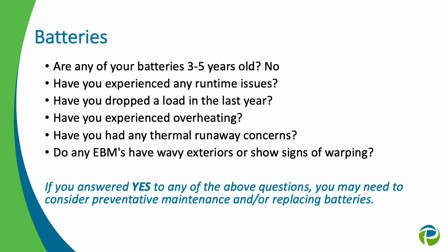And thermal runaway can be really dangerous because if you think of a chain of batteries overheating, that's just one big hot mess of a line, and that can cause fires very, very quickly, much more quickly than a smaller battery overheating. So thermal runaway is a huge concern. If you have any overheating batteries, you've got to get those replaced immediately. And do any of the batteries have a wavy exterior or show warping? Again, that's a big sign that something is wrong.